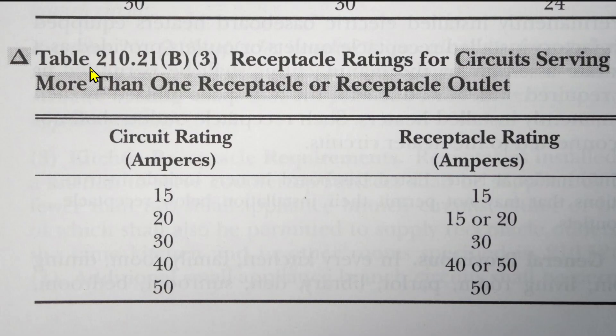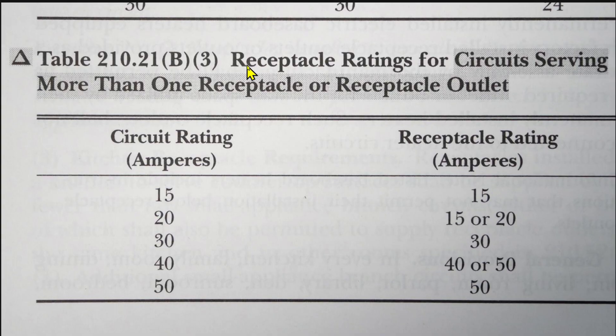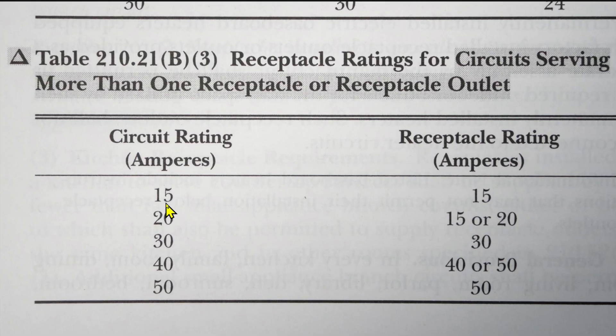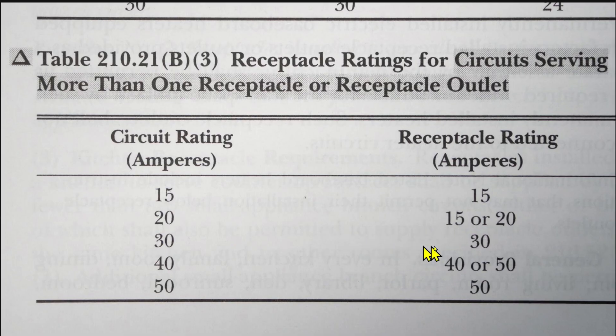Here we are at Table 210.21(b)(3) — with a delta symbol indicating a 2023 change. This covers receptacle ratings for circuits serving more than one receptacle or receptacle outlet. The table shows: a 15 amp circuit rating must have a 15 amp receptacle rating; a 20 amp circuit rating can have a 15 or 20 amp receptacle rating; 30 amp is 30; 40 amp is 40 or 50; and a 50 amp circuit rating needs a 50 amp receptacle rating.